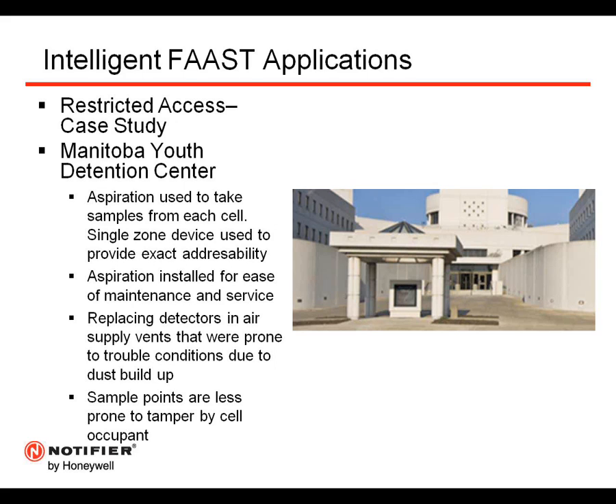The Manitoba Youth Detention Center, this is a restricted access case study that we have up in Canada. They used FAAST for all the reasons that Dan said. It also gave them addressability so that they knew exactly which cell would have the problem should a problem occur. This also makes it easier for them to maintain and service the device. With the pipe network, you're able to remotely clean the pipe network should it get clogged up from the device, which would be, in this case, outside of the protected area, by either vacuuming out the pipe after you've disconnected it from the unit or blowing it out with compressed air.